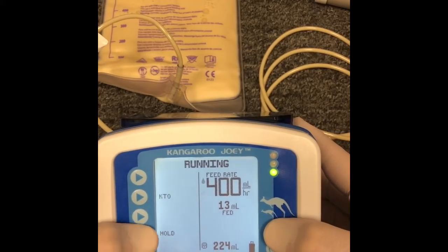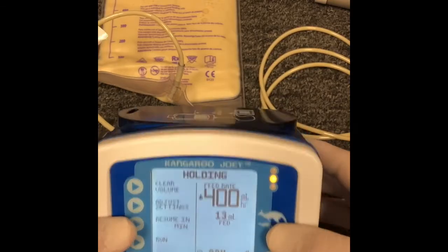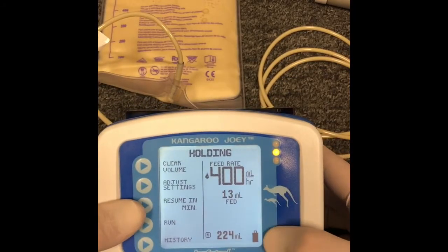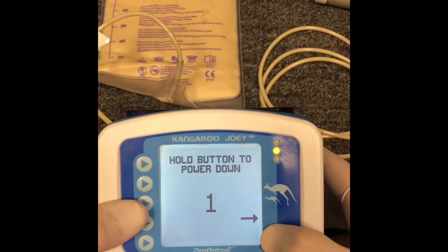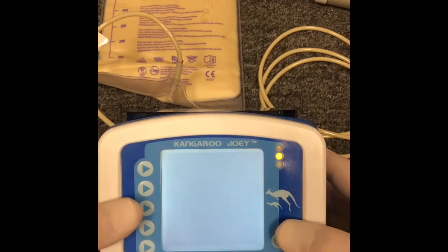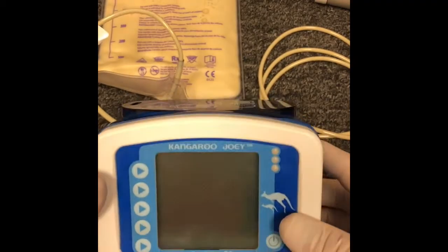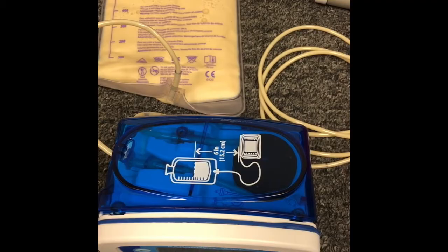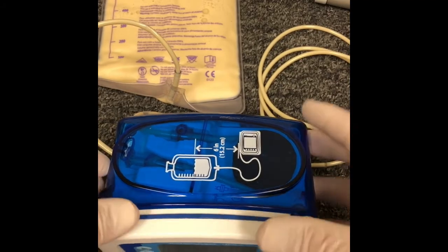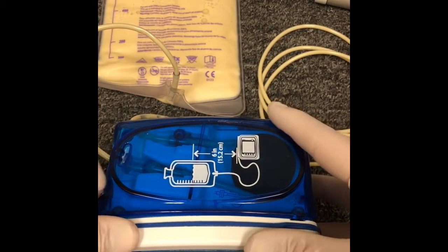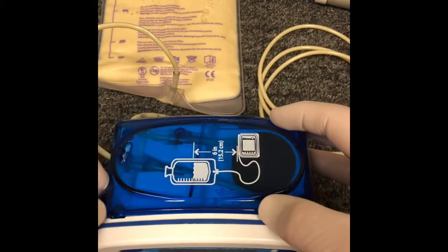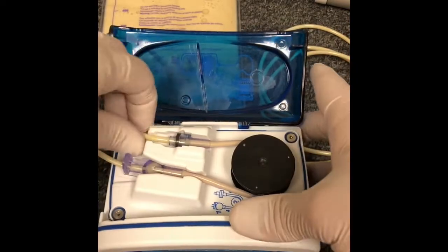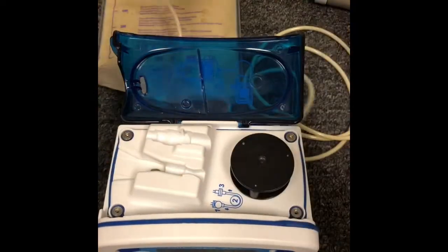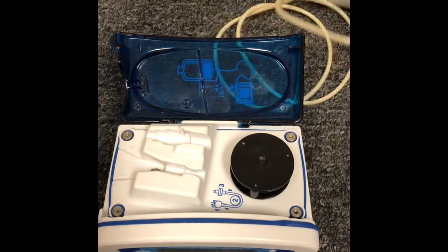And the next thing I want to show you about this pump, I'm going to go ahead and pause it and turn it off. This pump has a unique feature that only this feeding pump has, which is it's able to use a dual bag situation. That means it has two bags on the same tubing, and I'm going to show you that in a moment. Let me get those bags set up—it'll be more clear as I get them set up. So let me uninstall this one and set it to the side.